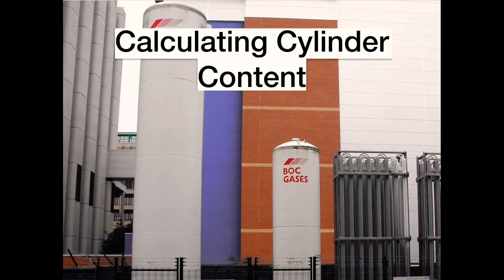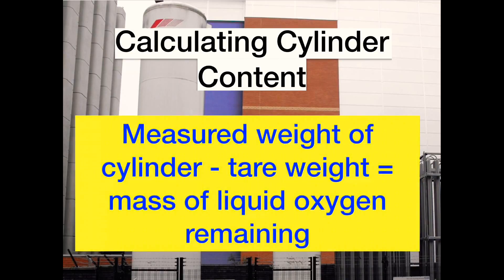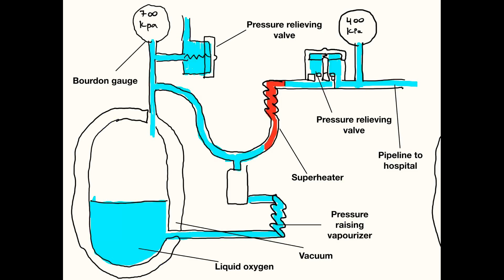The amount of oxygen remaining in the VIE is calculated from its mass. The mass of the empty cylinder, also known as the tare weight, is subtracted from the measured weight of the cylinder, with the difference being the mass of liquid oxygen remaining.